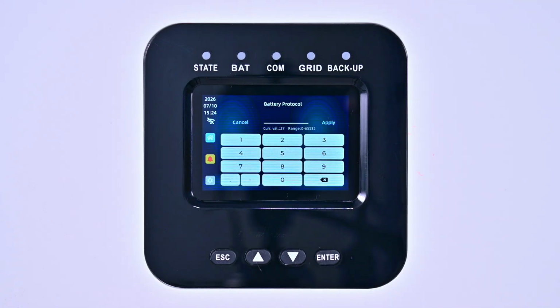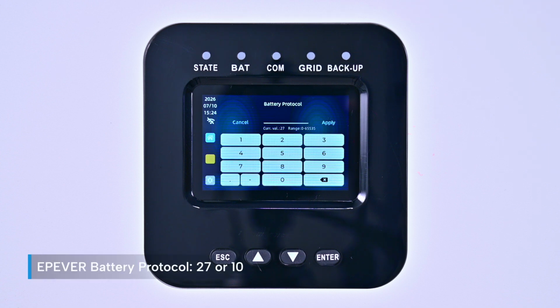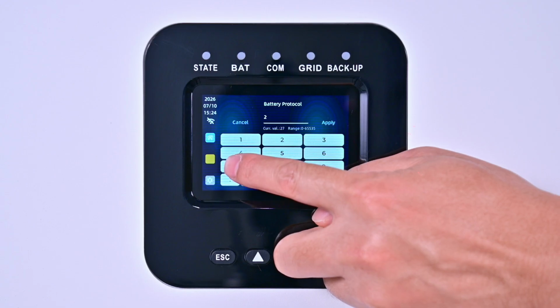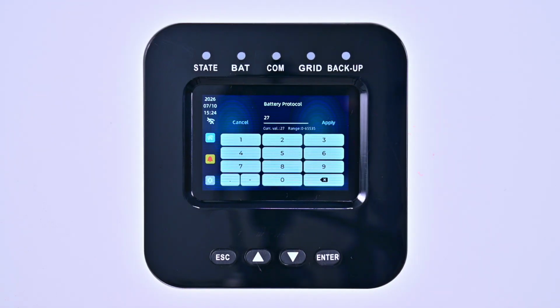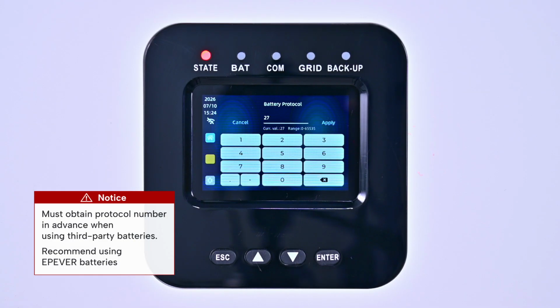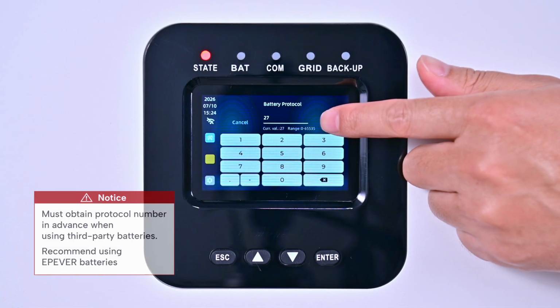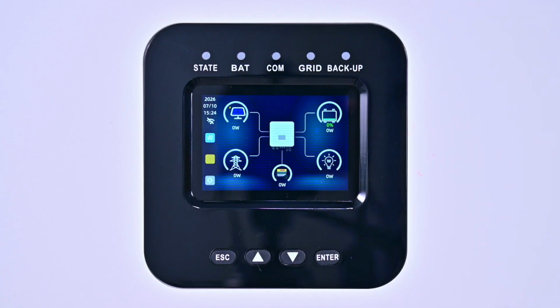Set the battery communication protocol. If you are using our Epever battery, please enter protocol number 27 or 10, then proceed to the next step. But if you are using a battery from another manufacturer, please contact your supplier to obtain the correct protocol number. For a safer power usage experience, we recommend using Epever batteries.